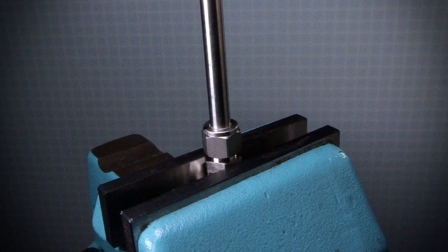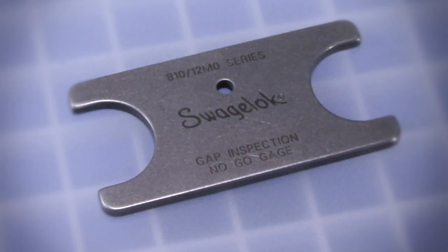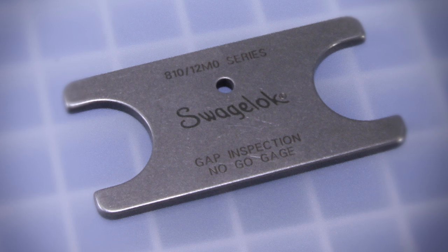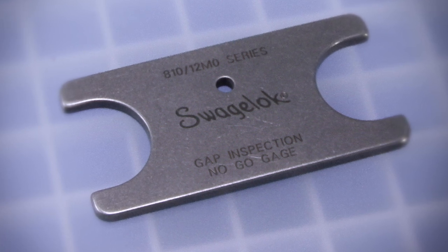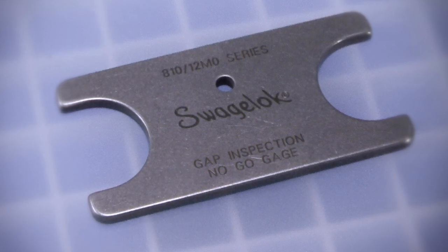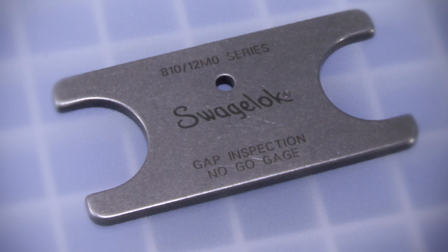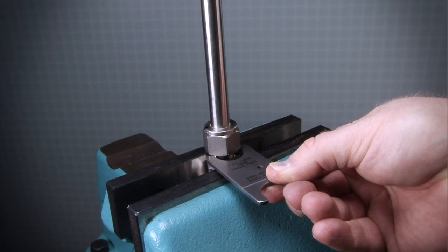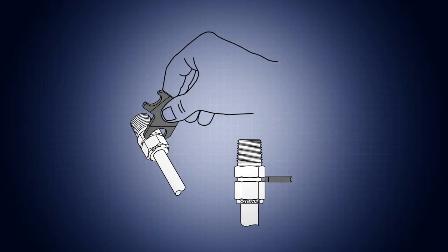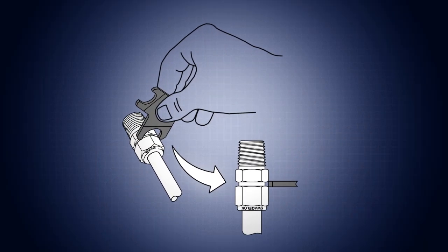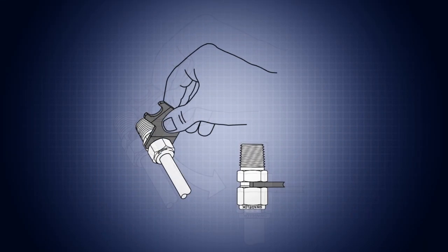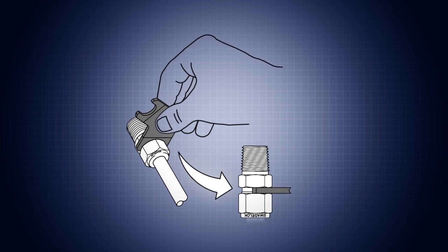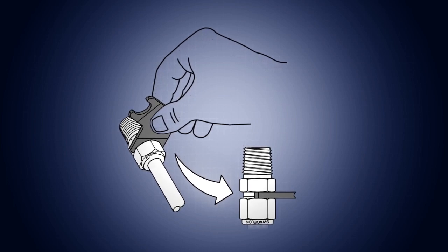Swagelok tube fittings and caps are recognized for their gaugeability. A Swagelok gap inspection gauge assures the installer or inspector that the cap has been sufficiently tightened. To use the gauge, position it next to the gap between the nut and the body. If the gauge will not enter the gap, the fitting is sufficiently tightened. If the gauge will enter the gap, then additional tightening is required.